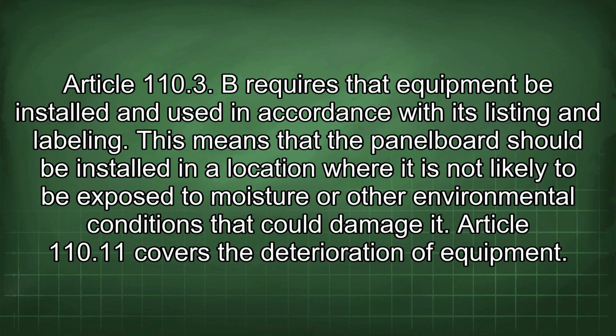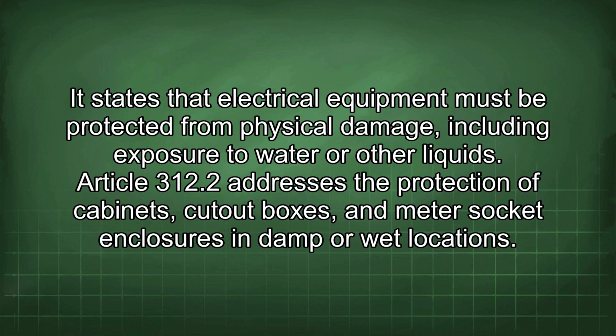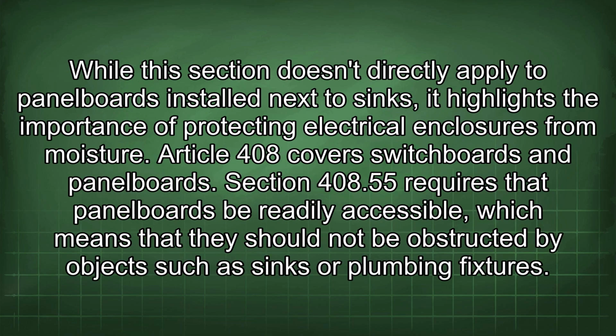Article 110.11 covers the deterioration of equipment. It states that electrical equipment must be protected from physical damage, including exposure to water or other liquids. Article 312.2 addresses the protection of cabinets, cutout boxes, and meter socket enclosures in damp or wet locations. While this section doesn't directly apply to panel boards installed next to sinks, it highlights the importance of protecting electrical enclosures from moisture. Article 408 covers switchboards and panel boards.